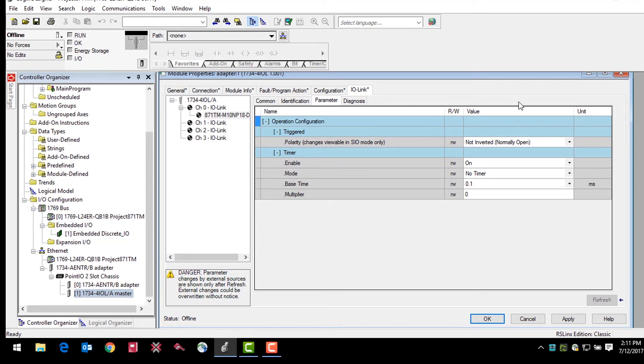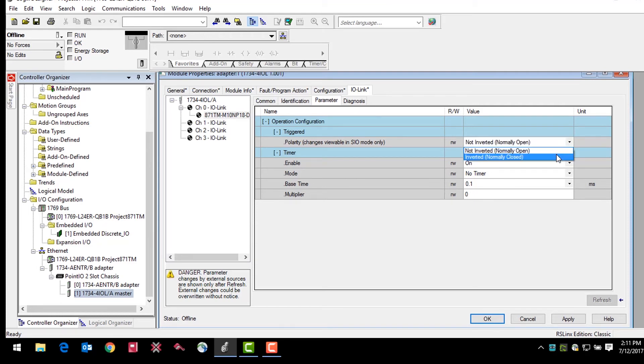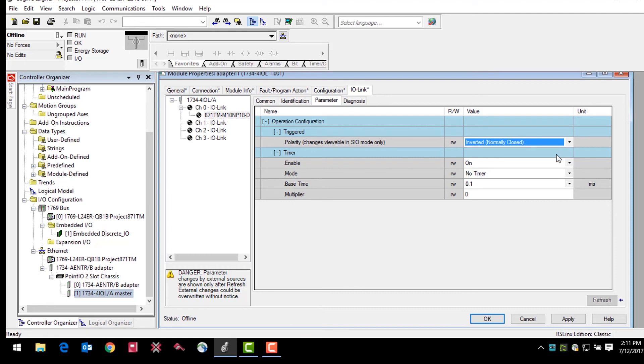The 871 TM sensor features the ability to change the output switching mode or the polarity parameter. The factory default mode is not inverted or normally open. When the sensor in IO-Link mode, you can change the polarity parameter to inverted or normally closed. The ability to change these factory default settings that normally would be non-configurable is a huge benefit of the IO-Link technology.